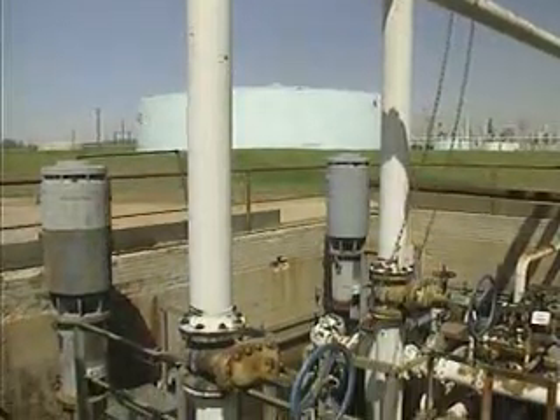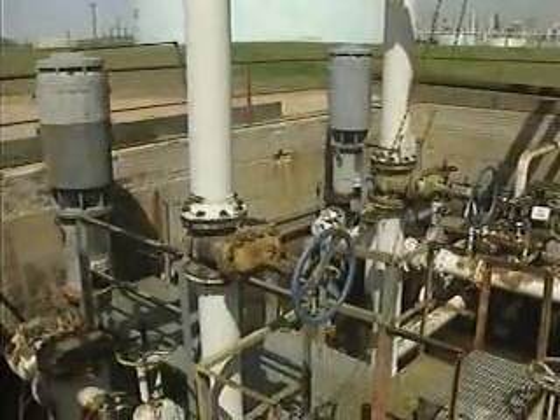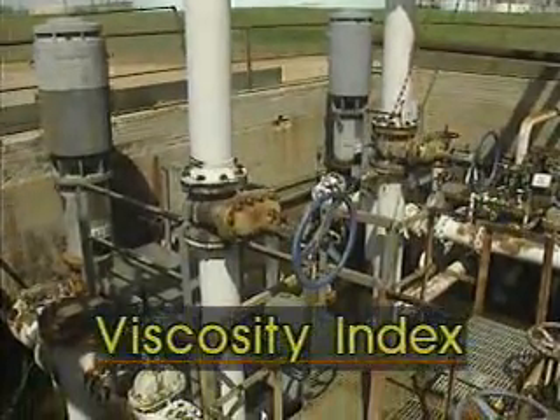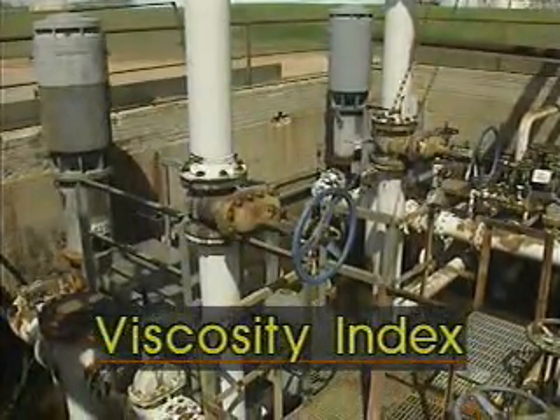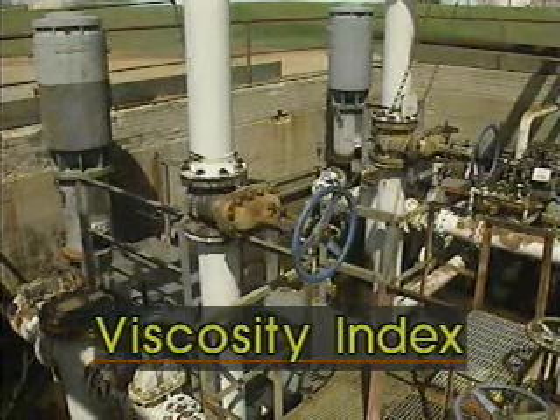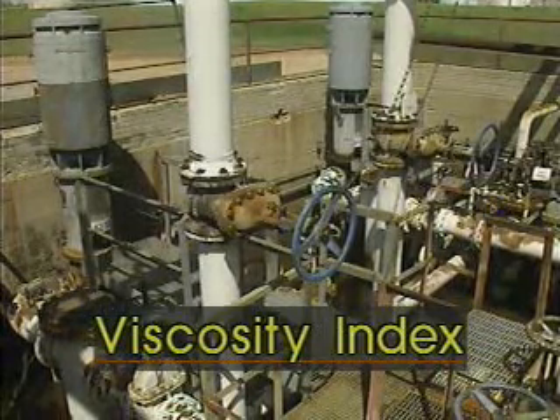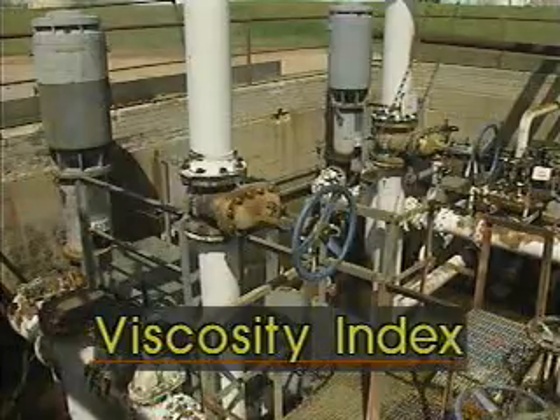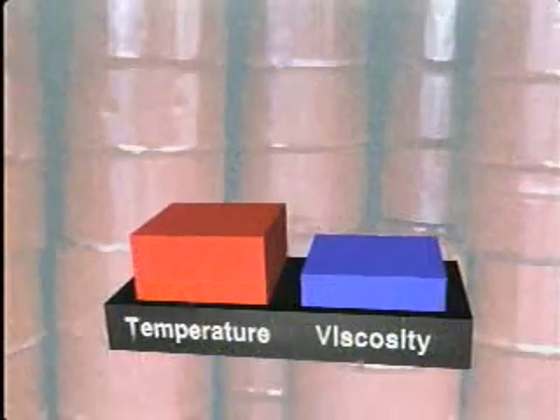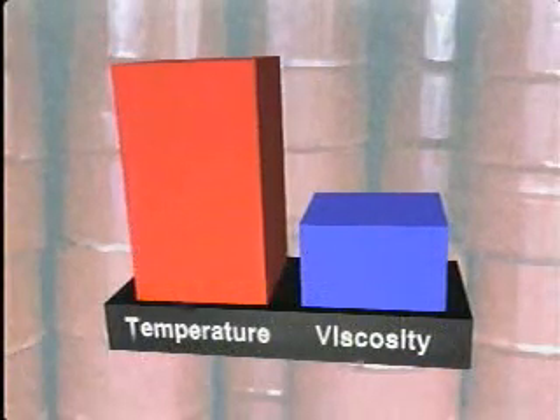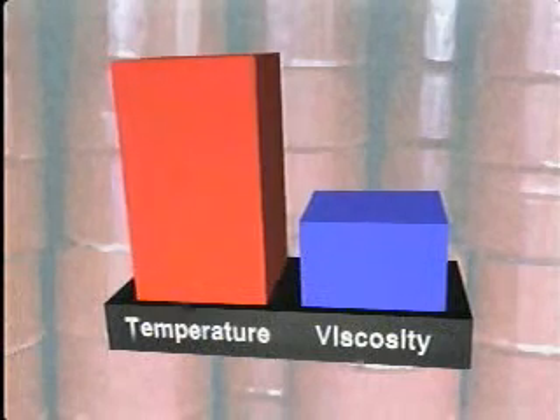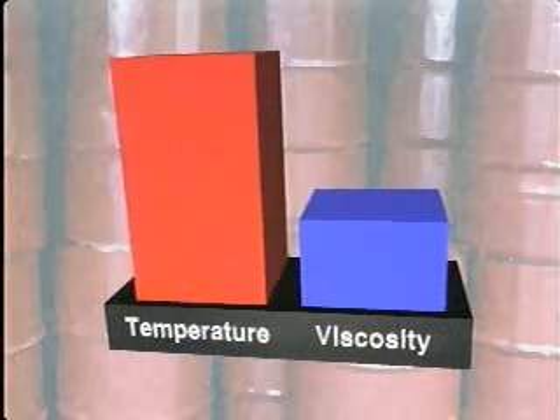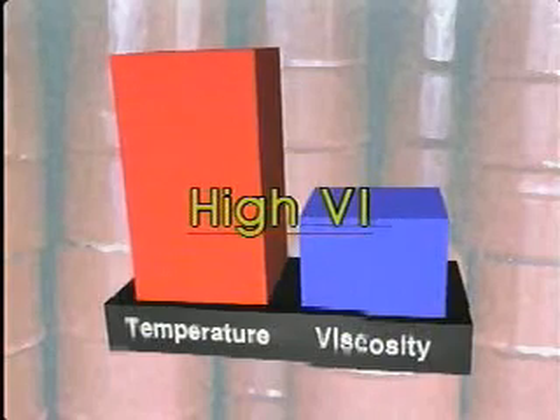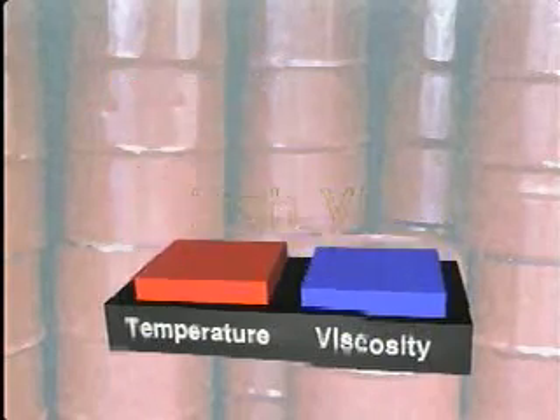If a lubricant is used where large changes in temperature occur, the lubricant's viscosity index is important. The viscosity index is a measure of the lubricant's viscosity change in relation to temperature change. If, when temperature changes a large amount, the lubricant's viscosity changes a small amount, the lubricant has a high viscosity index, or VI.